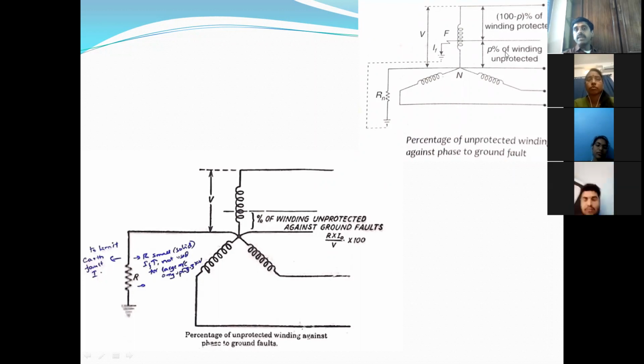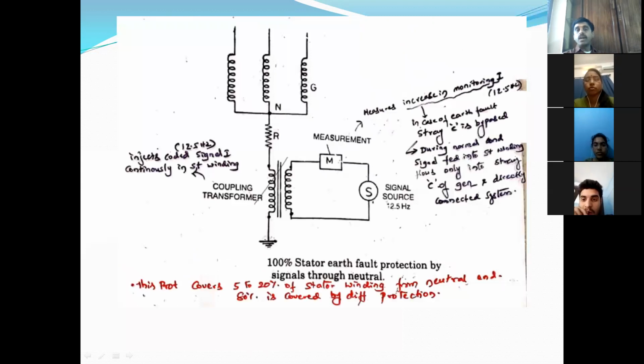So you can see another way of representing this. P is the percentage of the winding unprotected. The remaining winding protected is 100 minus P percent. Rn is the neutral resistance. We will see two problems on this percentage of the winding unprotected that you will get in the exams also. Before that, let us see how to get 100% protection, because we are getting only 80 to 85% of the winding protected. How to protect the remaining 15 to 20% is the scheme.